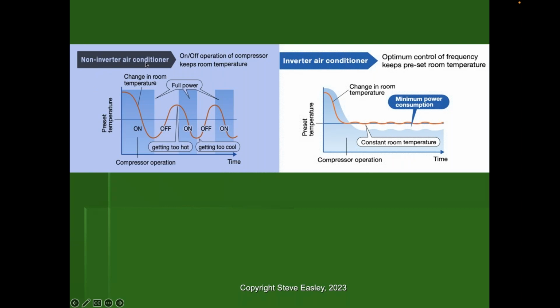If we look at your typical non-inverter heat pump or air conditioning system, the thermostat calls for heat, it turns on, heats or cools everything down, and then you get these huge, big temperature swings. And it's drawing full power at all these times. So this is not exactly grid friendly if you've got 5 houses on a transformer that are all trying to do the same thing, right? So you have these big temperature swings.